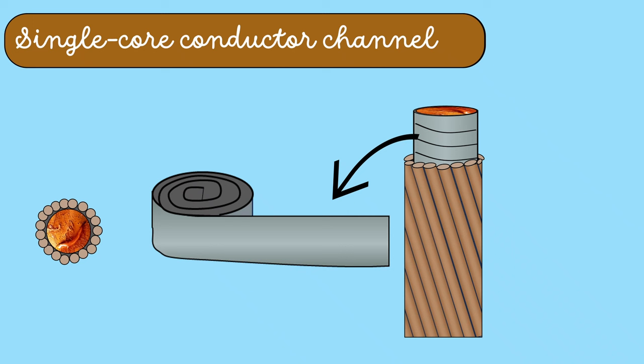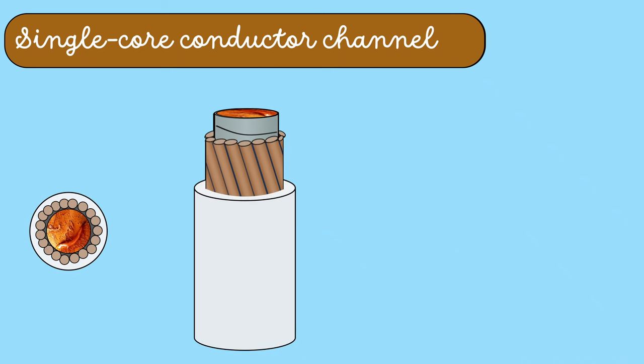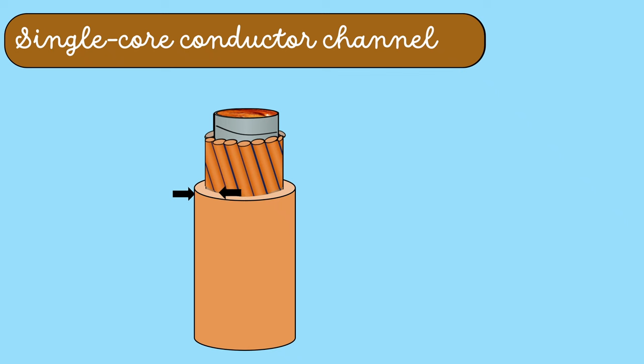As the channel is made of spiral steel tape, it allows the oil to percolate between conductor strands and wrapped insulation. Oil compresses the layers of the insulation and is forced to avoid any voids that may be formed between the layers.